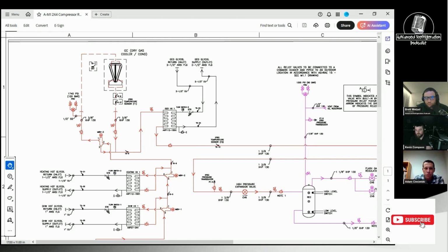The problem is if you shut it off in the summertime, you turn it back on and the fans don't respond right away. So the way to overcome that is just startup settings. You got to build a little control logic in there to say, hey, if the rack starts up, manually override the fans, push them to 50 or 75% or whatever for one minute, let things stabilize, cool down, and then release the PID. So that helps a lot.